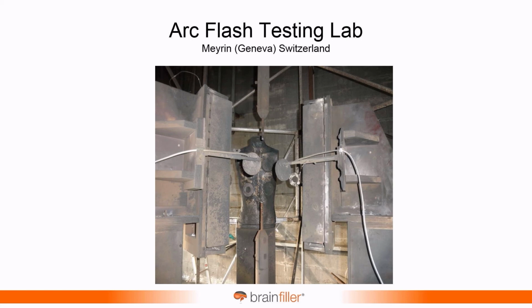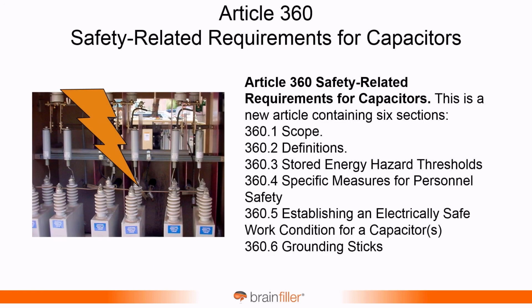And in fact, this is the test setup. This was in Geneva, Switzerland. I was there recently. There are a couple of labs that will do this. The big one is actually in Canada. There's a lot of testing there. So this is a calorimeter that measures the energy, and then you have opposing electrodes where you put a trigger wire, and that initiates the arc flash right there. And then you have the fabric samples of the garments on the panels that are spread equidistant around there.